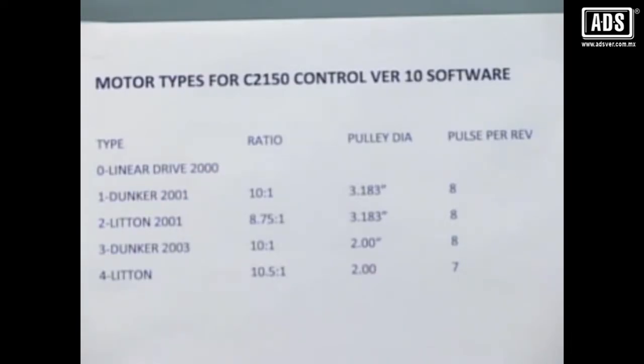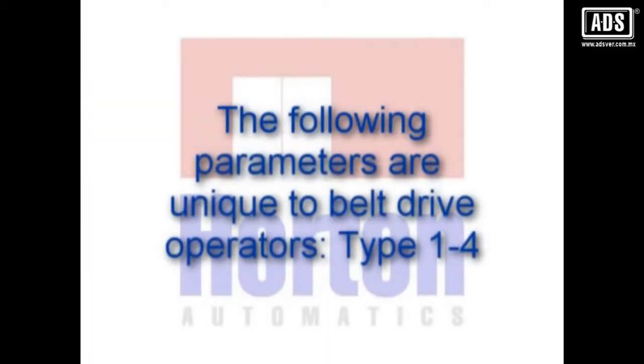When the type is selected, the appropriate data is loaded into the factory defaults. See the type table. Always push the door slowly from full close to full open and back to check for any mechanical issues or other obstructions before applying power. The following parameters are unique to belt drive operators, type 1 through 4.